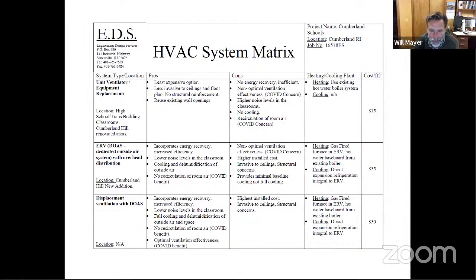Yeah, I agree. It's difficult to implement cooling with a unit ventilator system. The only way you could really do it in this situation would be to provide an additional DX coil within the unit ventilator, and then have a separate air-cooled condensing unit for each unit ventilator up on the roof.